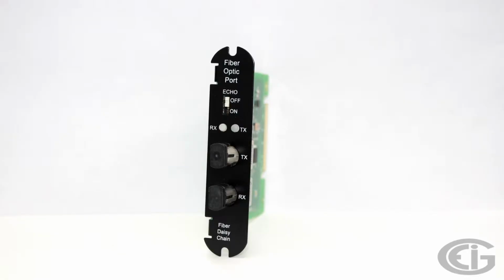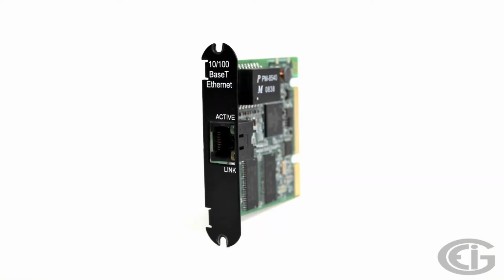The final two cards are used for communication. The first is a fiber optic card, which mimics RS-485 communication, but has the advantage that you will be able to use fiber for the cable run between devices. Finally, we have our Ethernet card, which allows you to use TCP/IP to interrogate and program the meter. This card also has a web server function, which allows you to see status and readings for the meter using any web browser.